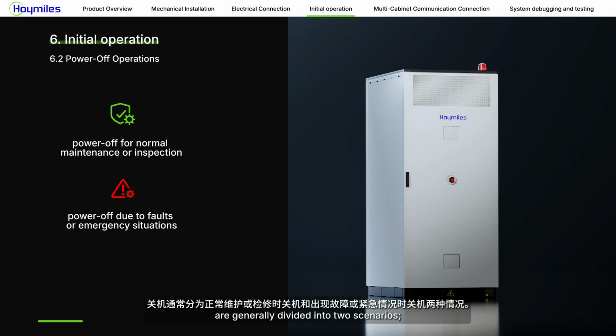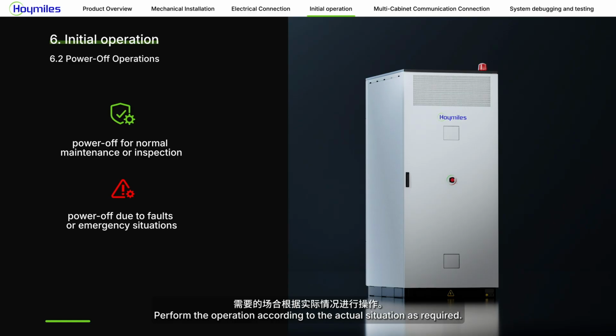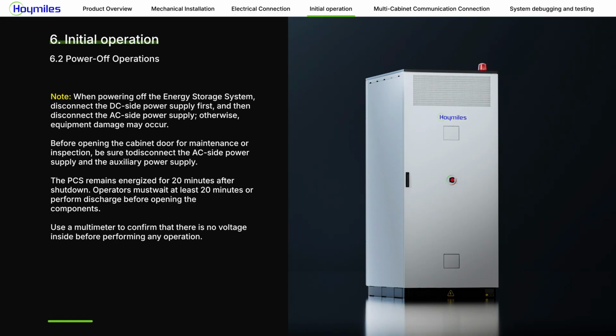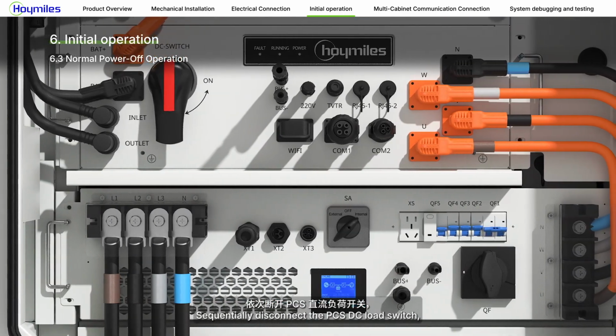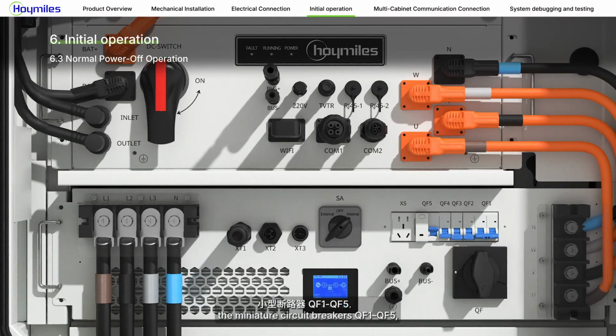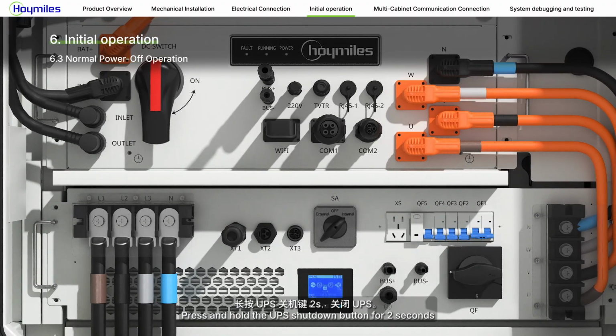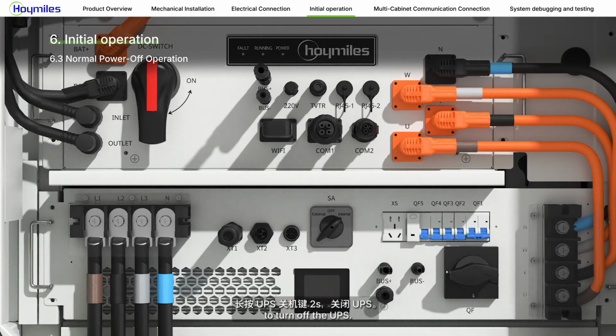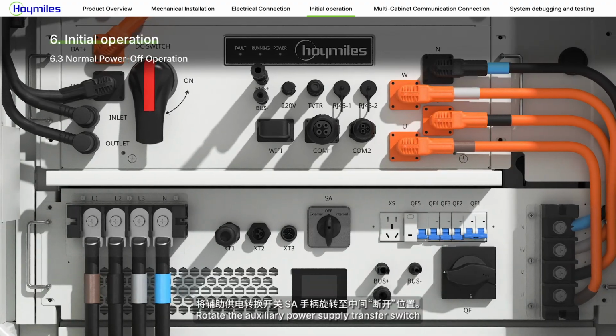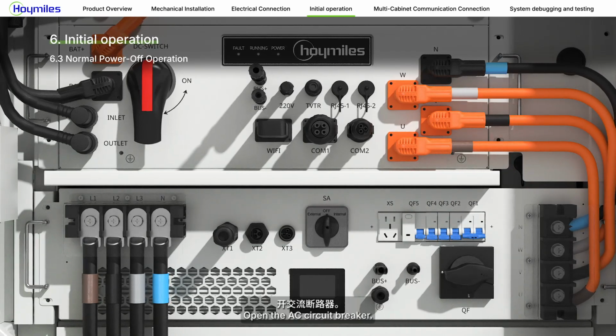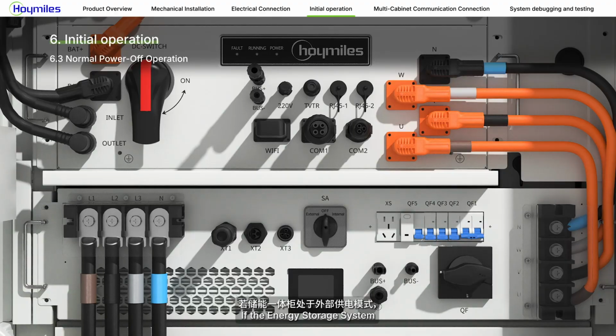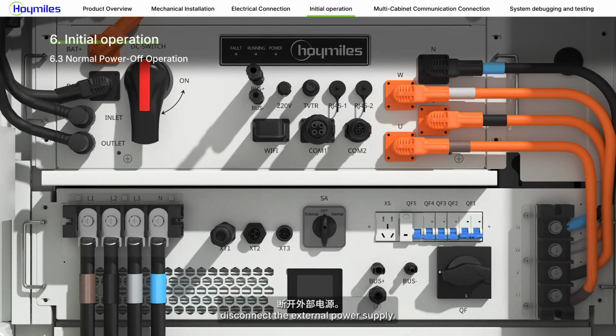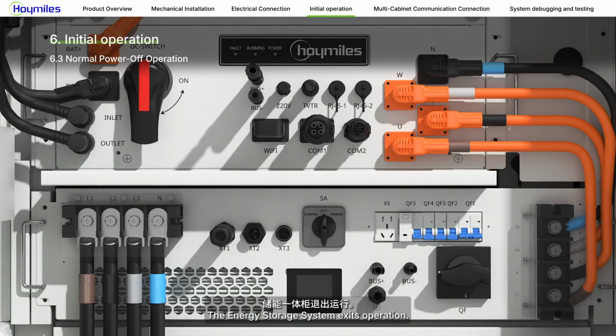Power off operations are generally divided into 2 scenarios: power off for normal maintenance or inspection, and power off due to faults or emergency situations. Perform the operation according to the actual situation as required. Sequentially disconnect the PCS DC load switch, the miniature circuit breakers QF1 to QF5, and the AC side main circuit breaker QF. Press and hold the UPS shutdown button for 2 seconds to turn off the UPS. Rotate the auxiliary power supply transfer switch SA handle to the middle off position. Open the AC circuit breaker. If the energy storage system is operating in external power supply mode, disconnect the external power supply. The energy storage system exits operation.